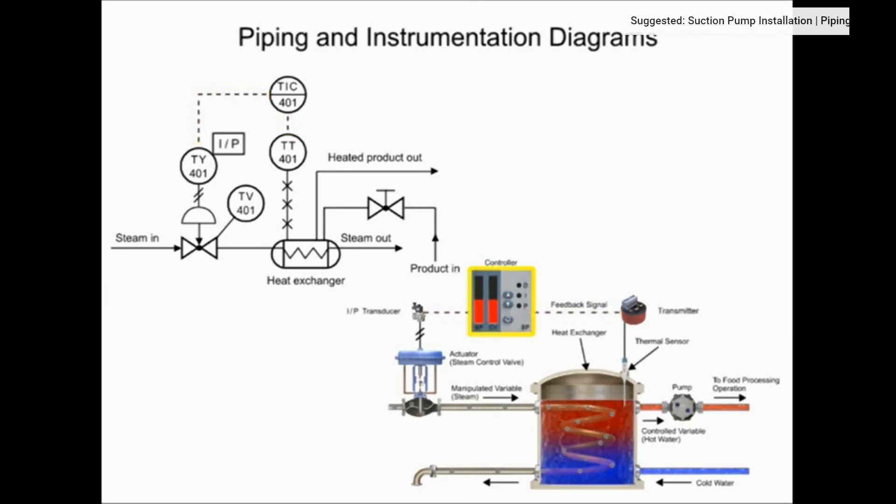The controller and indicator is the instrument where the transmitter sends an electrical signal and is shown in the functional identifier as the second and third letters, I and C. Balloons with a solid dividing line indicate that the instrument is board mounted.